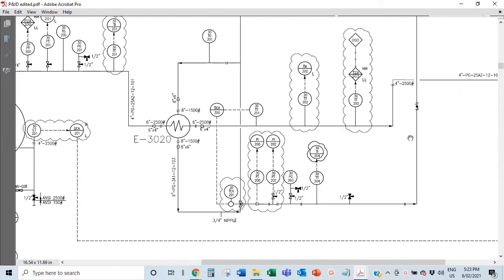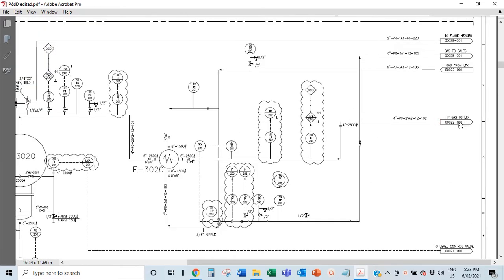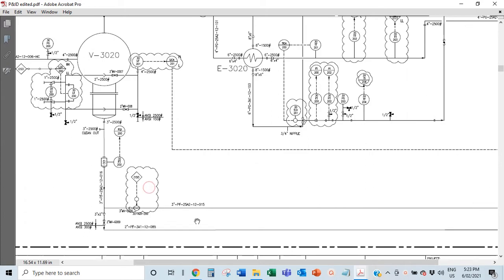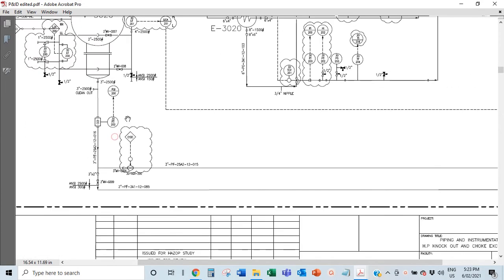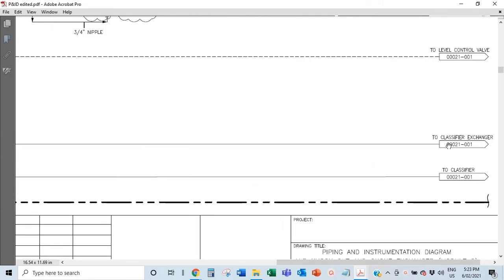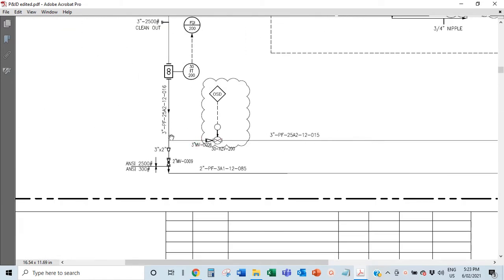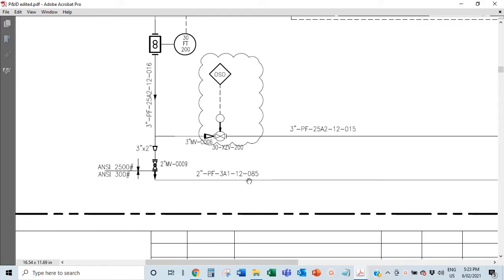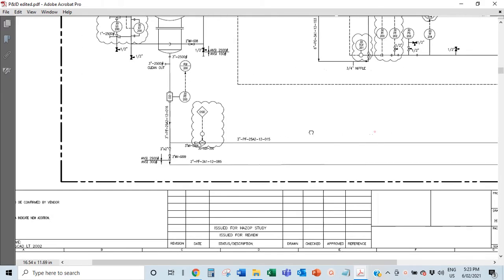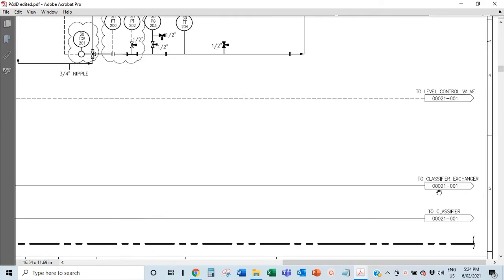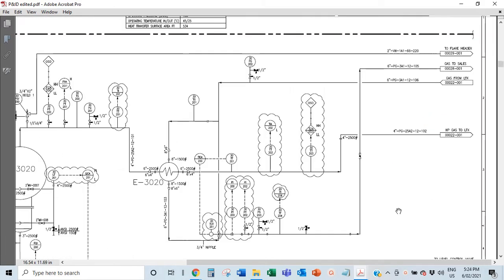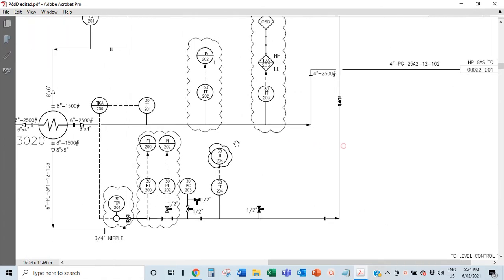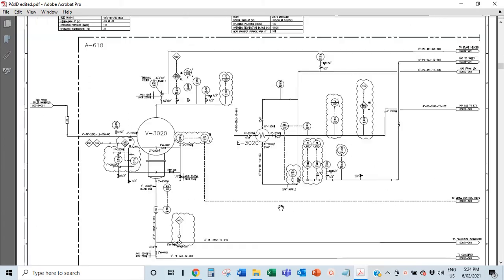When you see vessels labeled as scrubbers or separators, that's what they do — they split phases. Three-phase separators separate oil, gas, and water, since production from the ground is a combination of all three, plus sand and impurities. So the gas flows out the top into the heat exchanger and on to the LTX, while the liquid exits at the bottom.